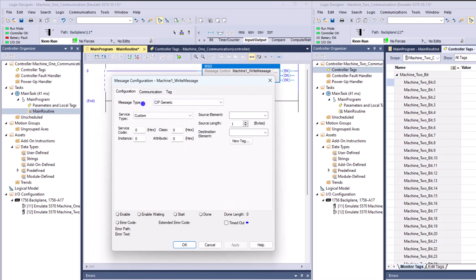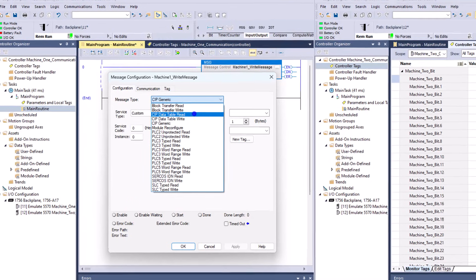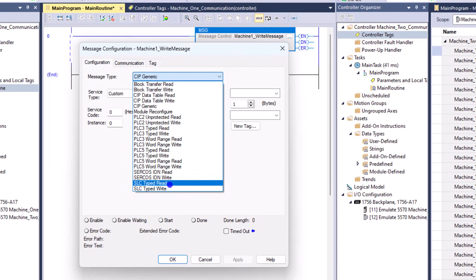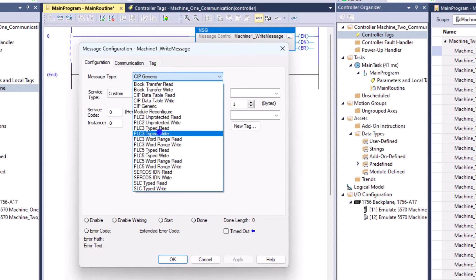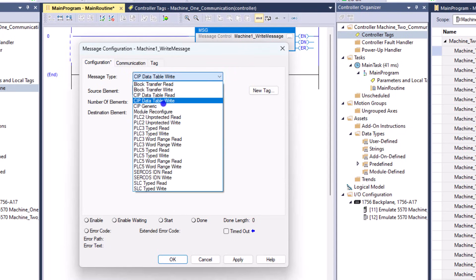When it comes to message type, the message type can be changed to many different things. We're going to concentrate on CIP, which is the ControlLogix platform, although you can write to PLC2, PLC3, PLC5, and Sercos - which would be like servos - and also the SLC, which is RSLogix 500. In our instance we're going to concentrate on CIP. I'll show you the difference between a CIP data table type - see how simple this looks: just a source and a destination.